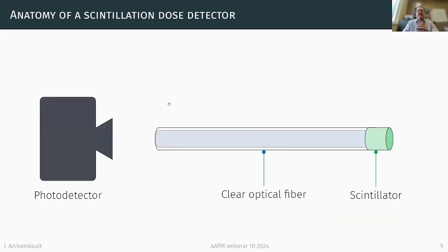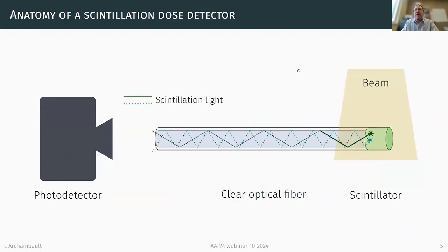So the anatomy of a basic plastic scintillation detector, there are many shapes and forms, but ideally it is composed of three components. First we have the scintillator itself, the plastic I just mentioned. It is usually coupled to an optical fiber to carry the light up to a photodetector that can be anything from a photomultiplier tube to a camera. So when we irradiate this detector, the scintillation light will be emitted and transported through total internal reflection within the optical fiber up to the photodetector.